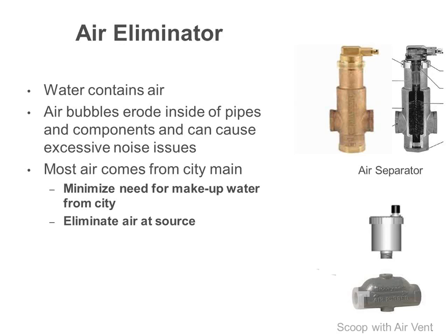Another common component of the expansion system is the air eliminator. Again, we talked about water a little bit. Water has air in it when it comes in. Air is not good in a hydronic system. It makes noises. Okay, basically you want to call it BBs in the piping or whatever. That air, when it gets into an impeller, can also cause cavitation issues and actually eat up the impellers. So we want to get rid of air. In the hydronic world, our fancy term is an air eliminator. Okay, basically what it is doing is eliminating air. Also in this drawing you see air separator, same thing. Those are the two that you really want to be using nowadays.